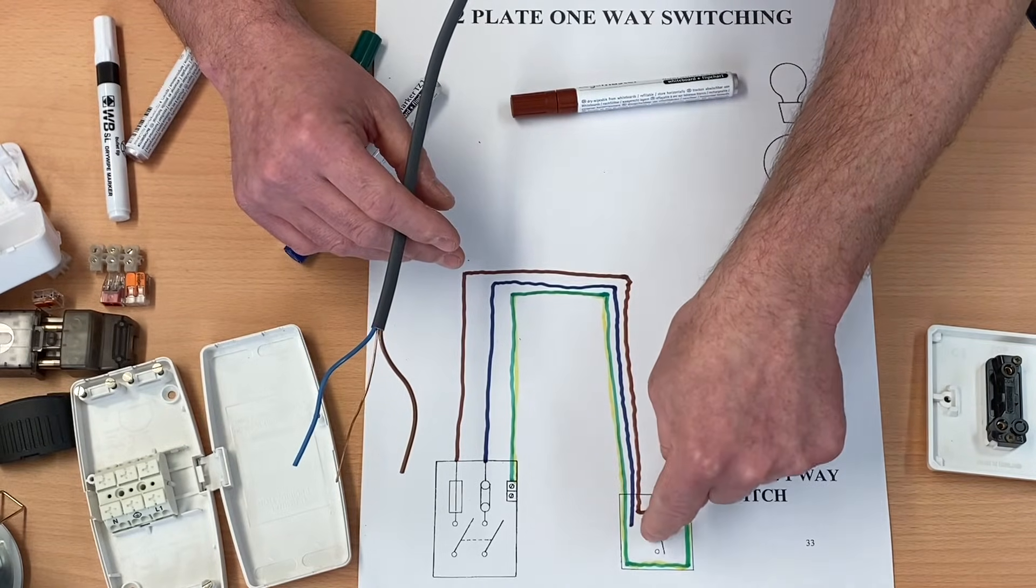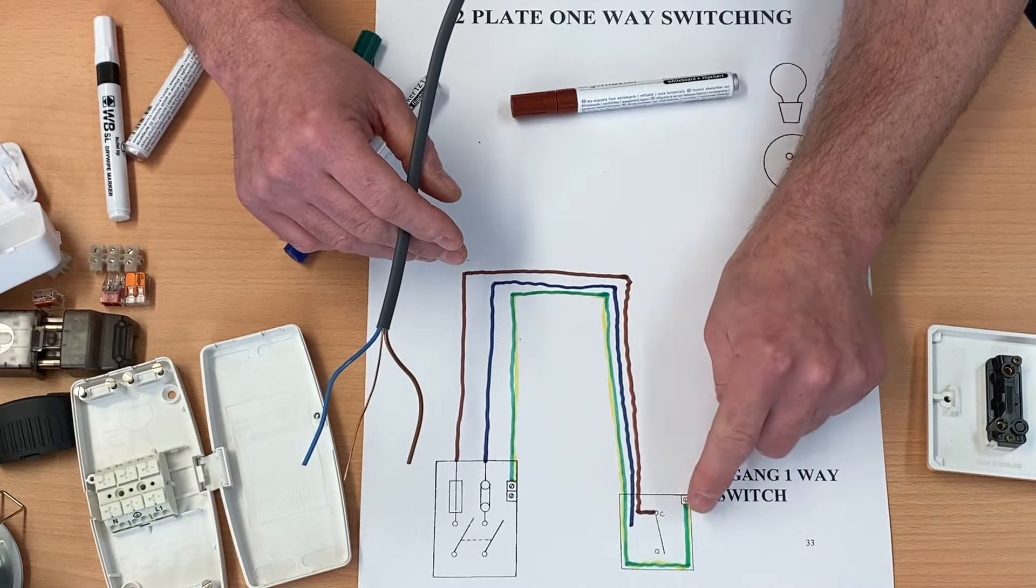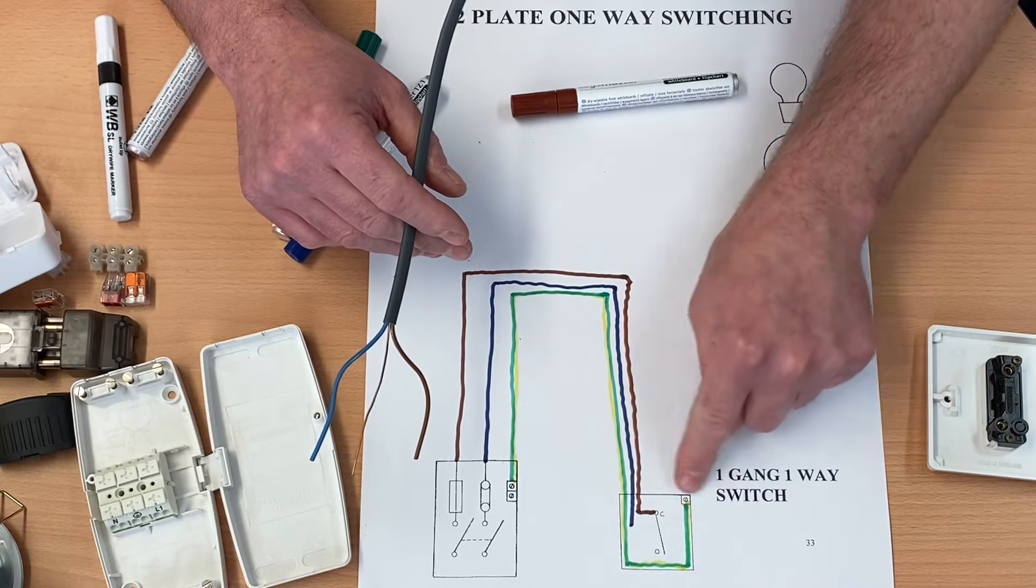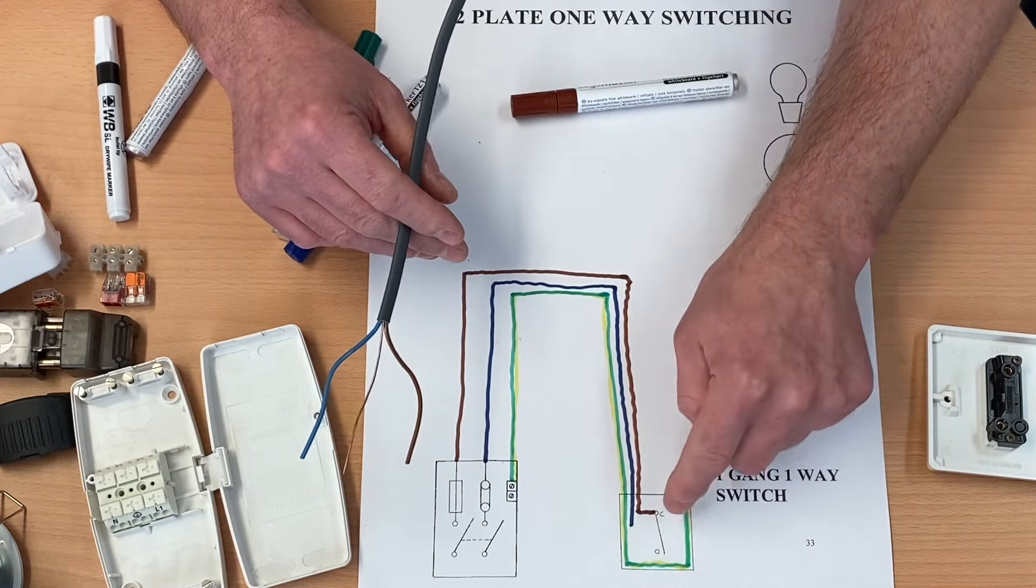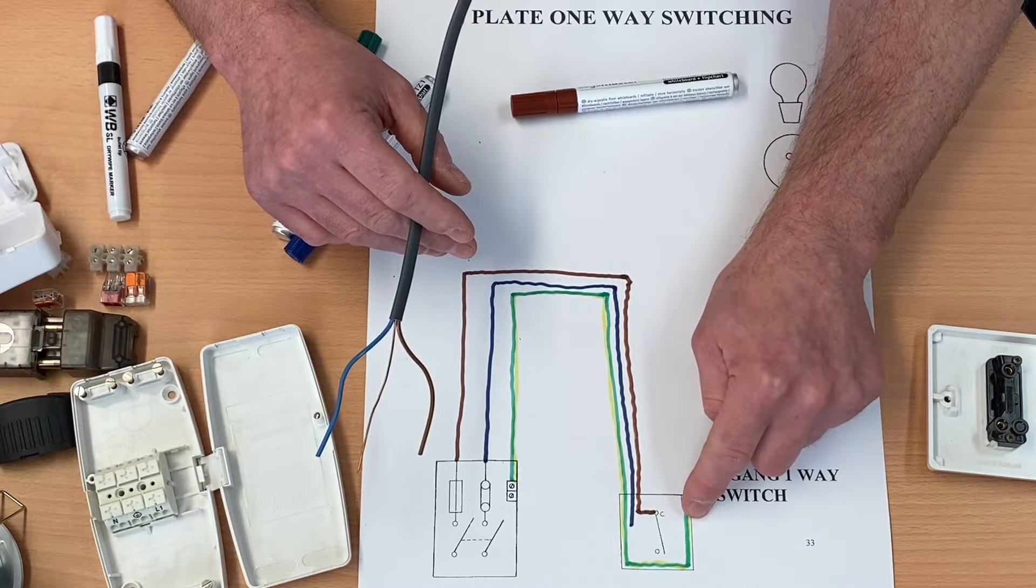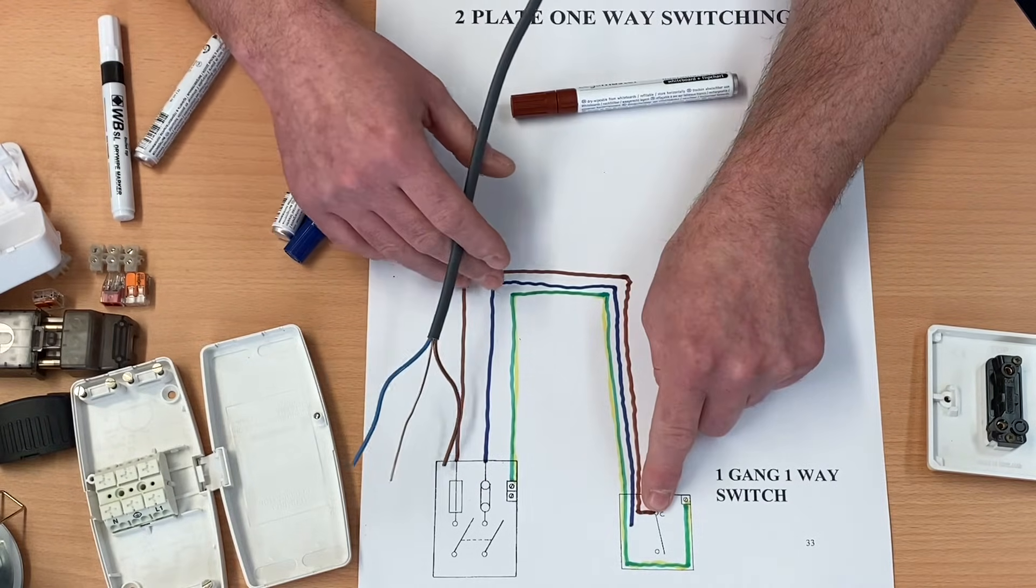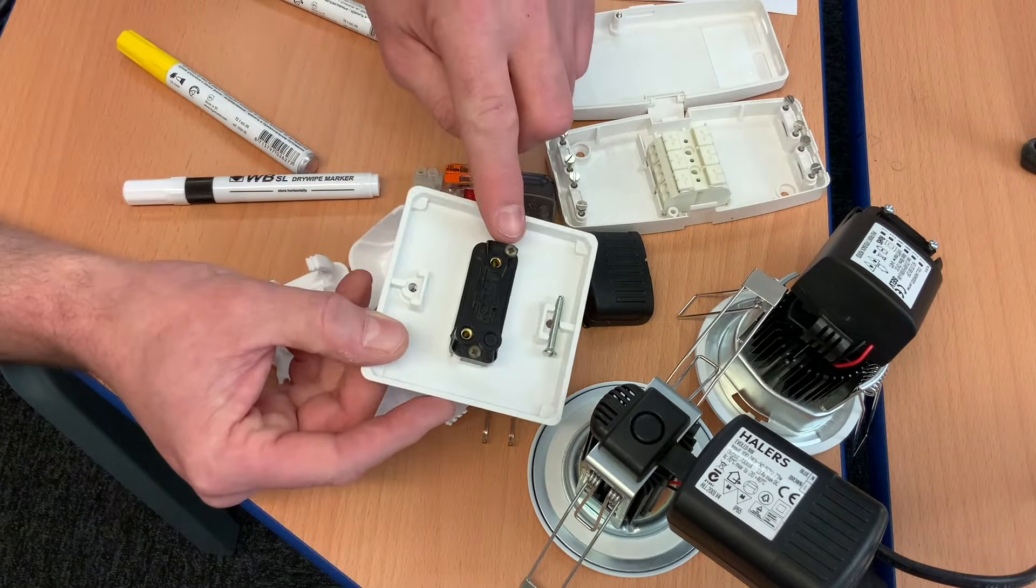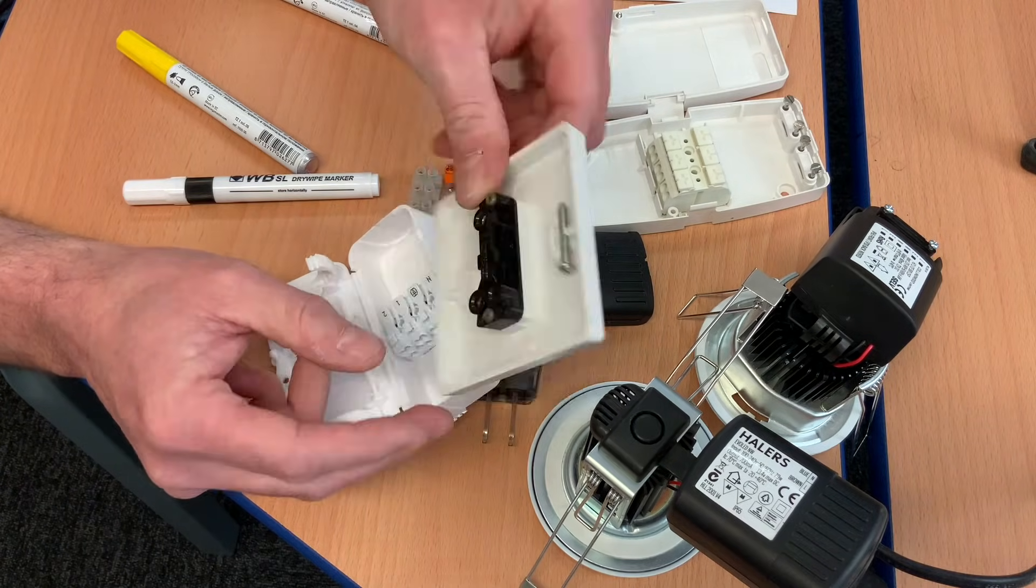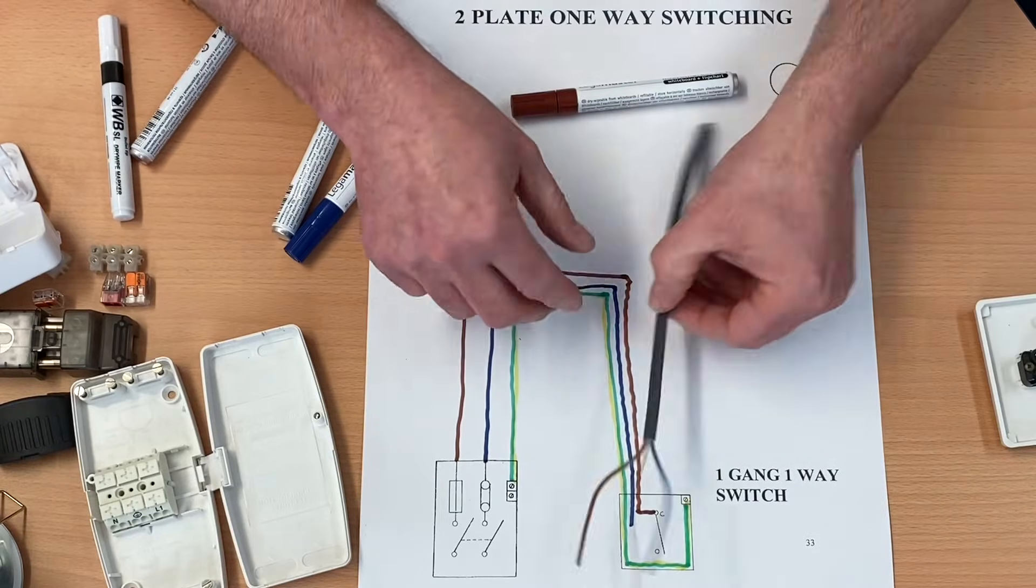And I've brought that cable directly into my switch. I've left the neutral at the moment floating. The CPC is connected into the earth terminal. We use plastic boxes at college. It could be into a metal box or a metal front. You need to make the CPC connection in the appropriate place. And my line conductor, in this case from the top of my fuse, comes directly into the common of my switch. So it comes directly into the common of my one-gang, one-way switch. So that's the first cable brought in.